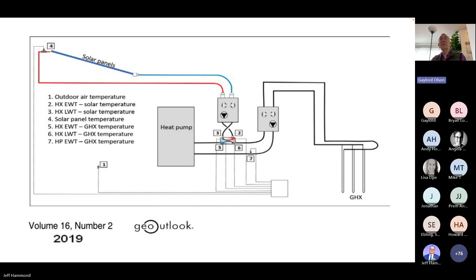A way to get to an optimum borehole size is to do multiple TRNSYS simulations over the long term and determine whether you have a limitation due to the cost of the boreholes, or a limitation in total cost of ownership because of higher electricity use. If your borehole heat exchanger (BHE) length is too great, the simulations will show you're spending too much money drilling boreholes. On the other hand, if the borehole length isn't long enough, you'll have a lower average coefficient of performance and higher electricity bills, so total cost of ownership becomes limited by electricity use rather than borehole length. So there's an optimum point.